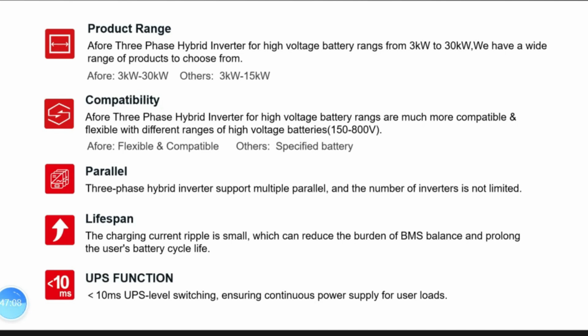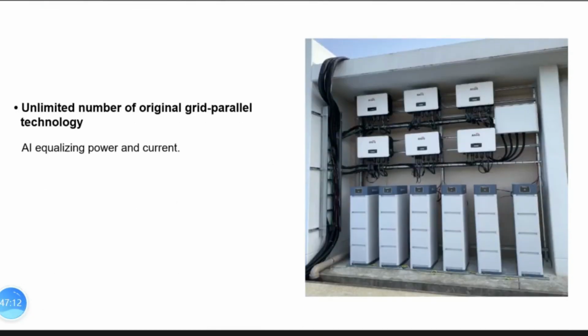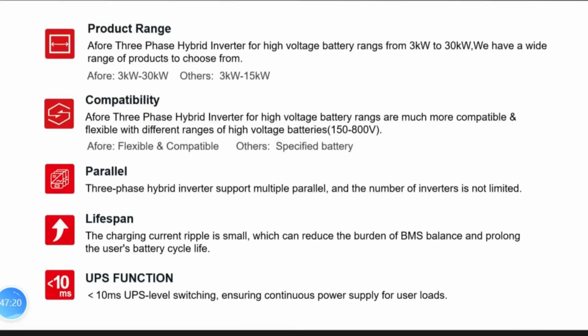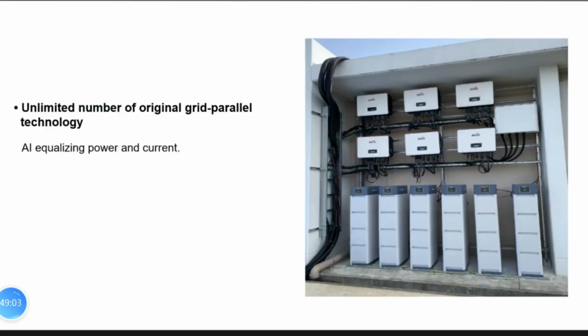So for parallel connections, we introduce the new technology of AI equalizing power and current. With this technology, for the three-phase inverter, especially for industrial applications, the parallel connection quantity has no limitation. For charge and discharge, the three-phase inverter has less charging ripple current. That means it will reduce the burden on the BMS and prolong the lifetime of the battery pack. So this part is finished.